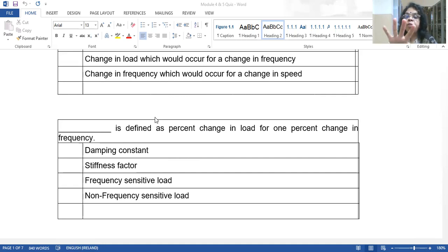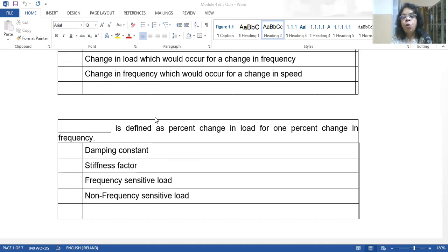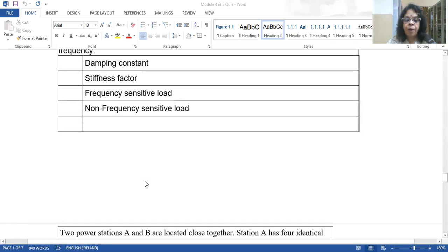Stiffness of the system indicates the change in frequency that would occur for a change in load. A stiff system keeps frequency nearly constant; a weak system has varying frequency. The damping constant is defined as the percentage change in load that causes a 1% change in frequency. For example, if the damping constant is 5%, a 5% change in load causes a 1% change in frequency — increase or decrease depending on load direction.